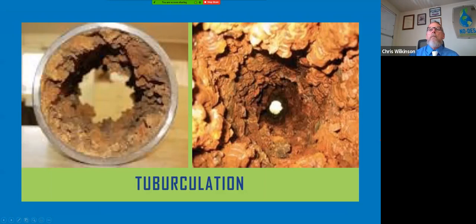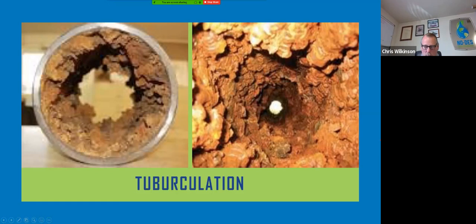Ice pigging, air scouring, a little bit does. We've noticed we've removed maybe 3 to 5% of it, very little. It's very hard to remove that. The jetting will remove it all, but the flushing only removes what the jetting removes. So with water main flushing, you're removing biofilm, iron, manganese, particulates, things like that. With the jetting, hooked up with the NODES flushing, is how you remove this ugly tuberculation. I hope that answers it.